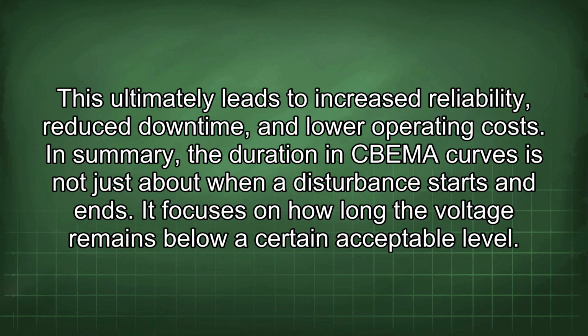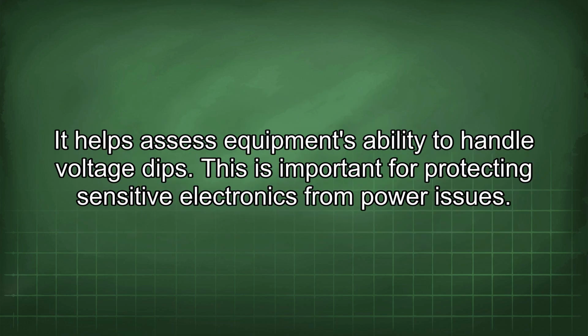In summary, the duration in CBEMA curves is not just about when a disturbance starts and ends. It focuses on how long the voltage remains below a certain acceptable level. It helps assess equipment's ability to handle voltage dips. This is important for protecting sensitive electronics from power issues.